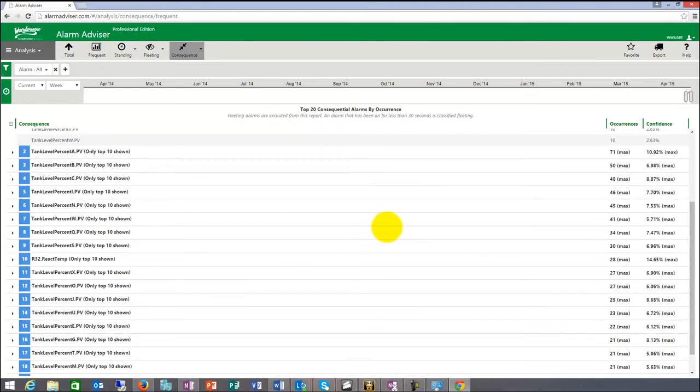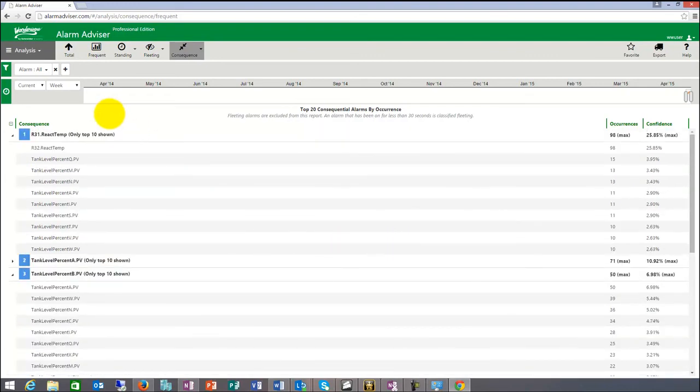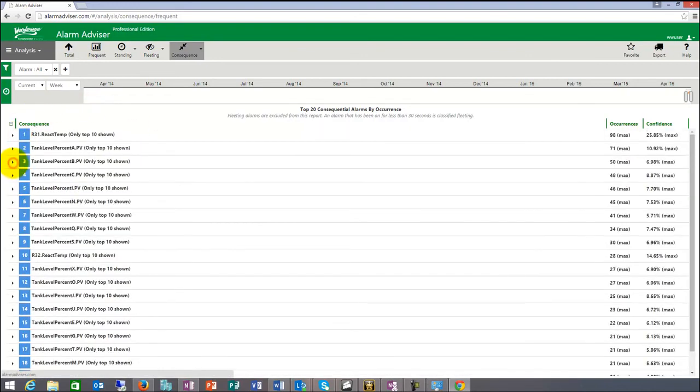But there might be some that have a relationship between each other where you can say, if this goes off 50 times and this goes off 39 times at the same time, are they related? Do they have something to do with each other? Can be, because remember, we can analyze multiple databases, so you might have 2 or 3 databases in this system that are shown on different terminal stations. For somebody that operates the facility, one might be the steam utilities, boiler utilities, production facility, packaging, and they all might be impacted by one event that ripples through the system.